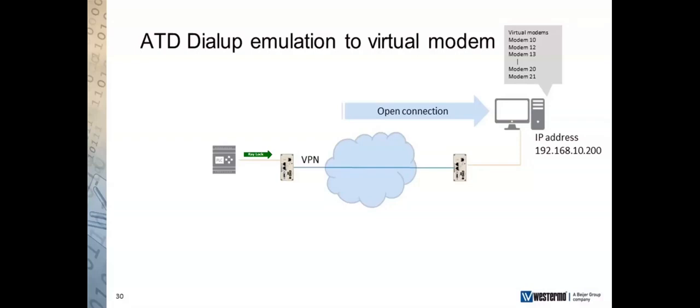So you start getting to a point where you can keep on opening and closing ATD connections almost in real time. We've got a few customers who actually do this. They've managed to step their scan rates up. They've improved their servers, admittedly. They've invested in new hardware to cope with all the extra data which is being gathered, but literally brought their scan times down to a fraction of what they would be over conventional analog modems. So it's not just a hindrance to have to change the technology in the middle. It can actually be a massive benefit to the data gathering process.